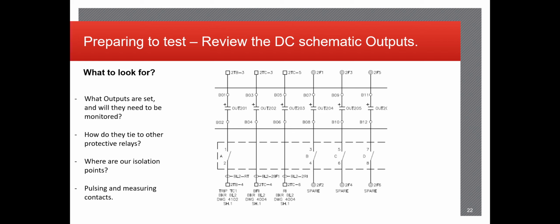properly, because in this case especially, the breaker failure initiate, if you run a test to trigger this output and it's not isolated properly, the other side of this terminal block may go to another piece of in-service equipment. So if you close that contact in, you might trigger a trip scenario on 2, 3, or 4 other relays and could kill half or possibly the whole yard.